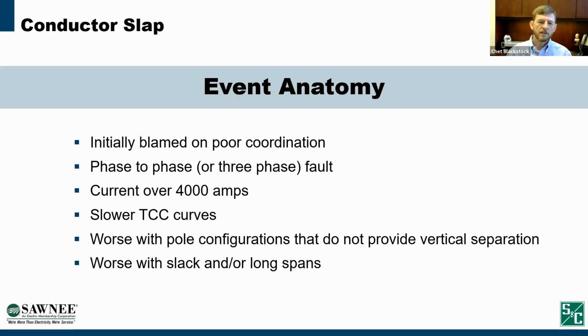Also, there's a time component to conductor slap. The faster you get that current off of the system, the less time that magnetizing force is in play, causing the conductors to swing. So the slower TCC curves made the conductor slap worse. And then I mentioned our pole configurations where we don't have adequate vertical separation. It makes it worse. And sometimes you just have some bad spans. So spans with slack, too much slack, or exceedingly long spans are more subject to conductor slap. Next slide.